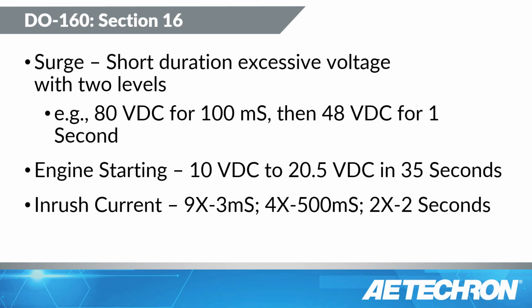In addition, there are surge tests, which are short durations, excessive voltage type tests. For example, I give one here that's for a 28 volt line. This particular category has you going to 80 volts DC for a tenth of a second, and then dropping down to 48 volts for 1 second. Now, there's no separation between those two. You have to do one followed by the other serially.